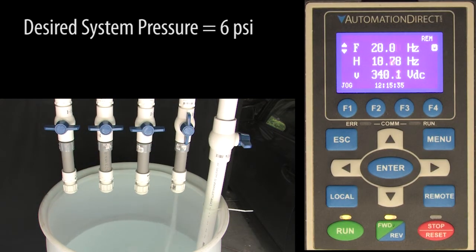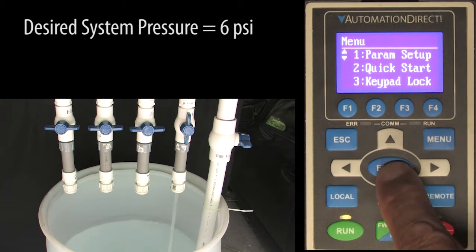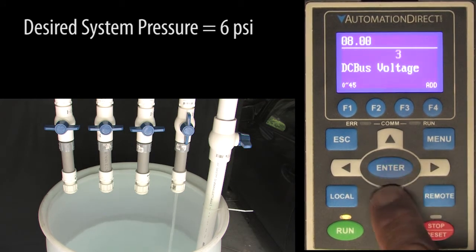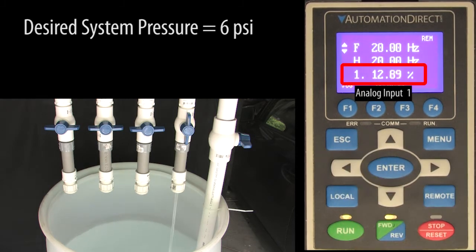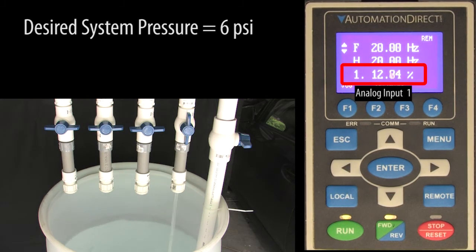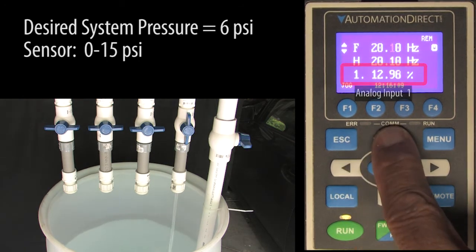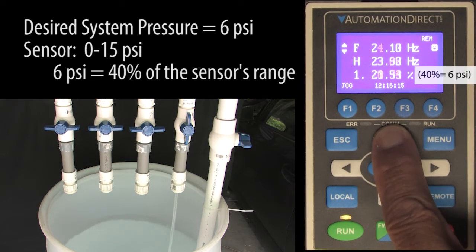We can monitor the feedback signal on analog input 1 right on the main display using parameter 8.0 and setting it to an 11. That shows us the sensor signal as a percentage. The sensor's range is 0 to 15 psi. The 6 psi we want is 40% of that range.